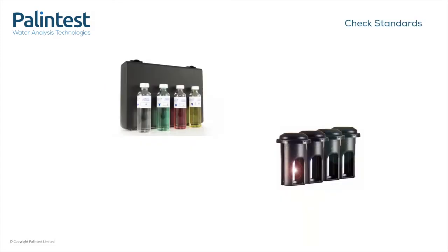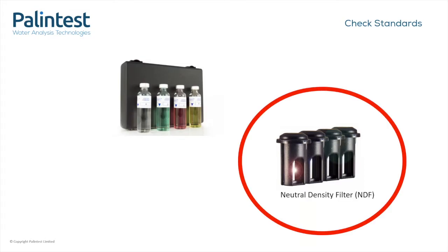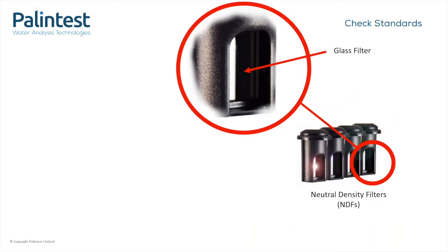Now, the other type of check standards that Palintest supply are neutral density filters, or NDFs for short. Neutral means that they absorb the same percentage of light at all wavelengths, and so they have no colour. In these holders are flat pieces of smoky looking glass.